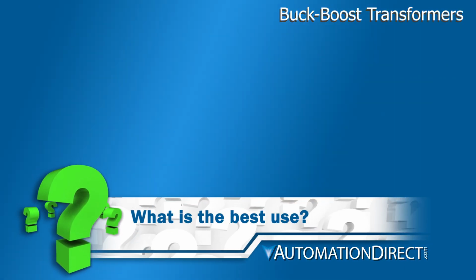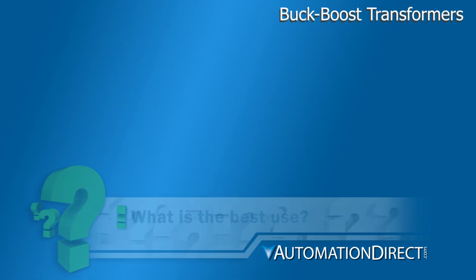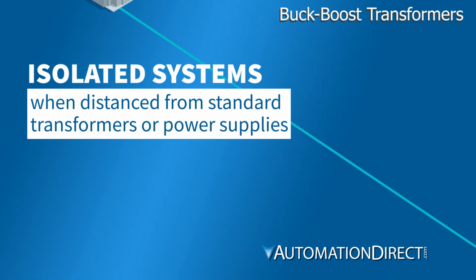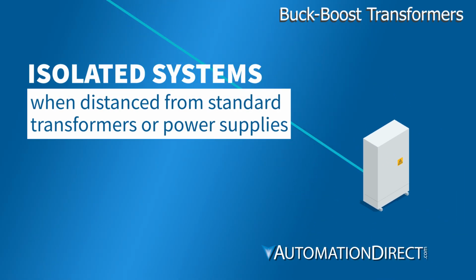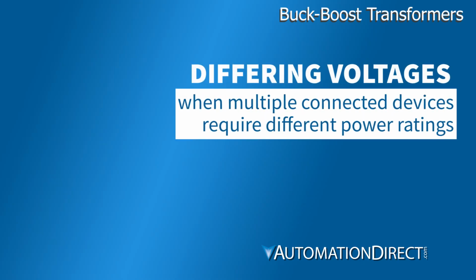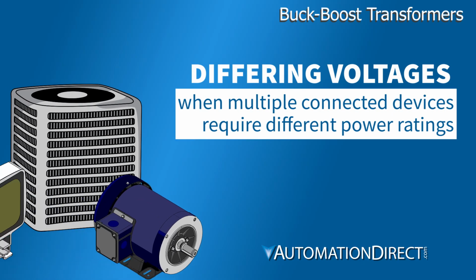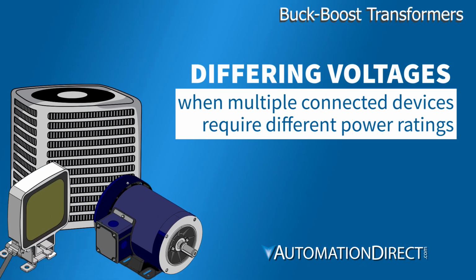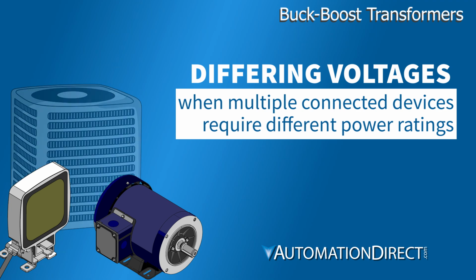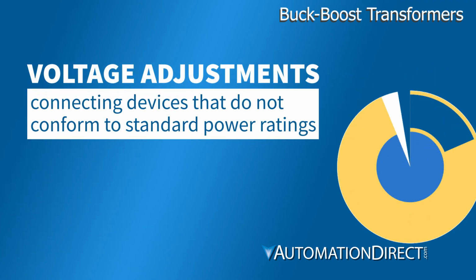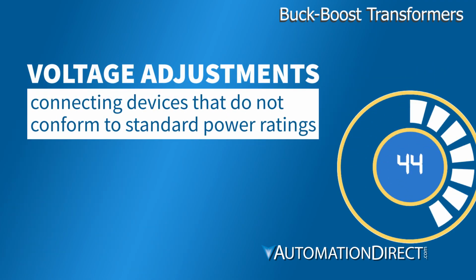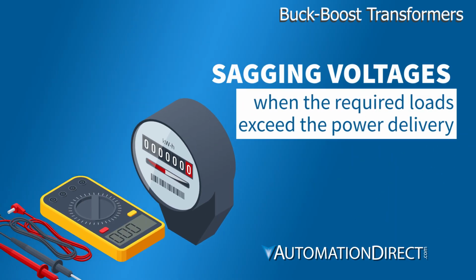Where are buck-boost transformers best used? They're best used in isolated systems far away from standard transformers, in power distribution to HVAC, small motors, or lighting systems which could require several different voltage ratings, where connected equipment requires a different or non-standard voltage adjustment, and in systems that experience sagging voltage.